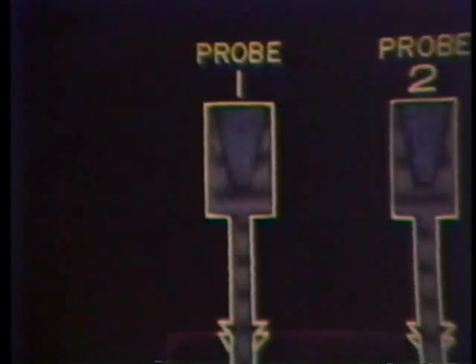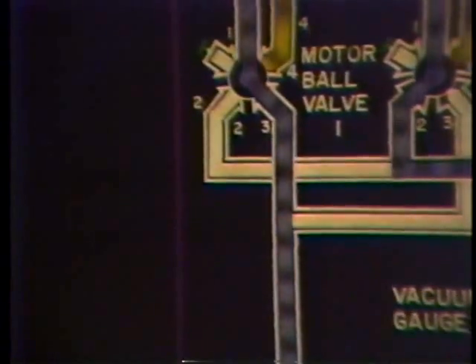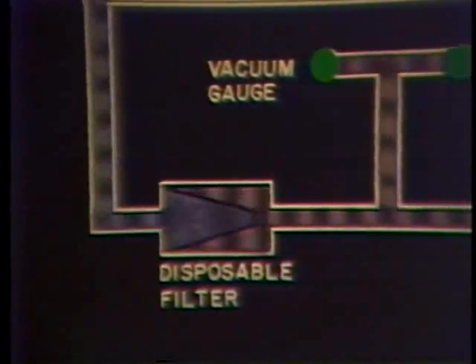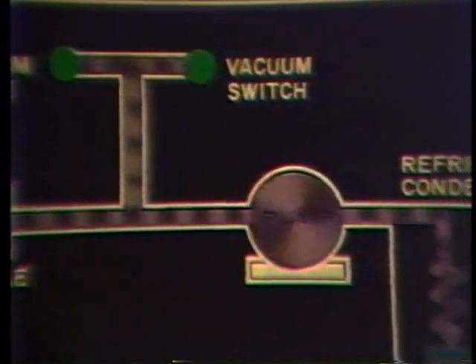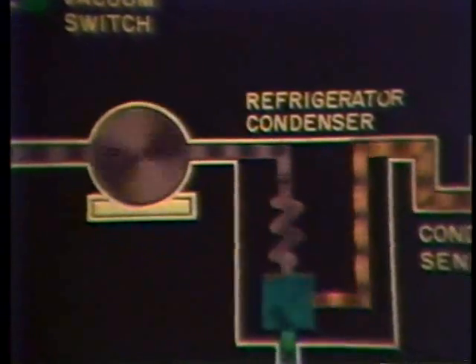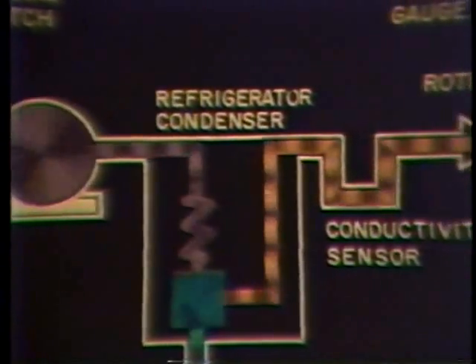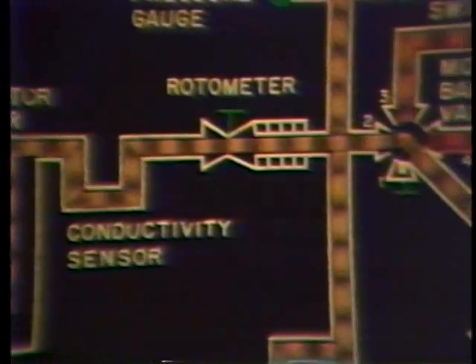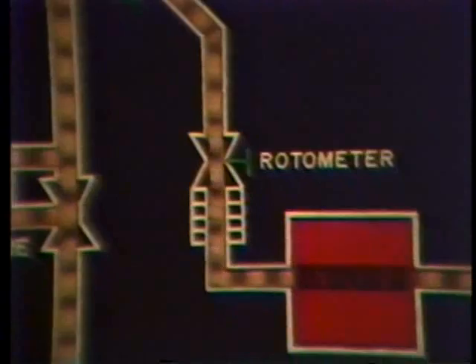Sample gas from a hazardous location is drawn through a probe tip filter which removes particles larger than 7/10 of a micron. Motorized valves select individual points for sampling and allow back purging and priming. Motive force for the sample is provided by a positive displacement pump, which then delivers pressurized sample gas to the refrigeration condenser for removal of moisture. A conductivity sensor ensures that nothing but dry gas is introduced to the carbon monoxide analyzer. After analysis, the sample gas is vented to atmosphere.